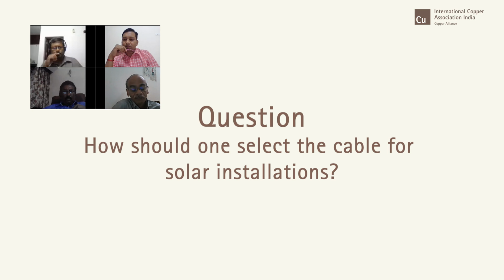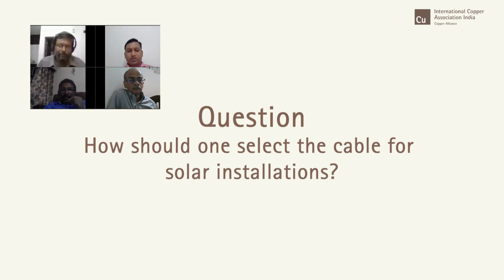So you have to definitely have an insulator which is stable with heat. It should be heat resistant, able to withstand maybe 60 degrees or whatever; the higher the temperature, obviously, the better it is, like they do in military grade and all that. Solar DC cable is definitely a superior grade cable. There are many international standards available for which an Indian standard is getting published, IS 17293. It is likely to be released in a week's time.